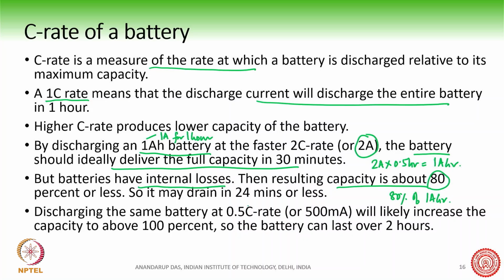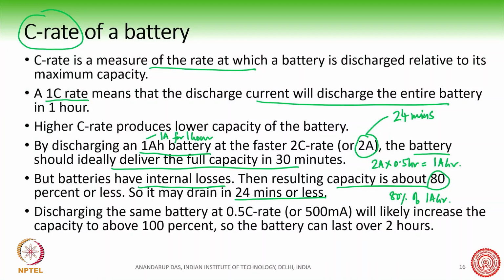So if you draw 2 ampere, it may only last 24 minutes instead of 30. If you increase that to 3 ampere, expecting it to last 20 minutes since it's rated 1 ampere hour, it actually won't last 20 minutes - it may last less than 10 minutes. So drawing more current from the battery makes it last much less than its rated capacity, which is why the C rate of the battery is very important.